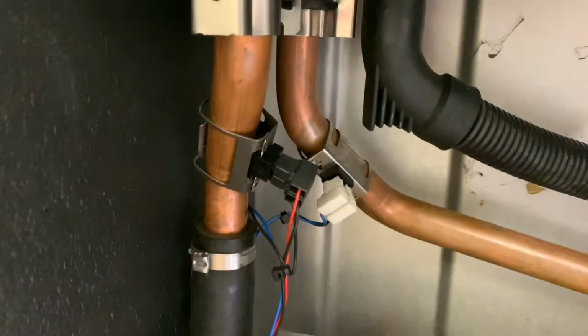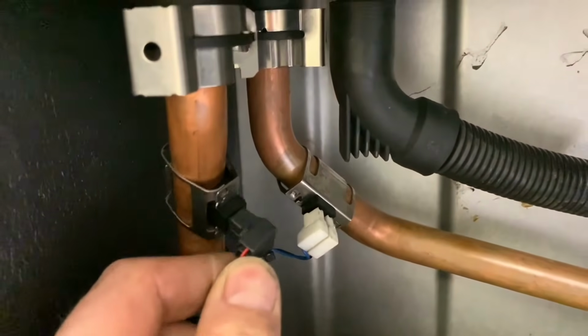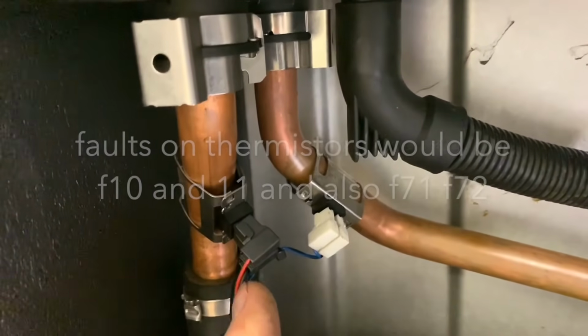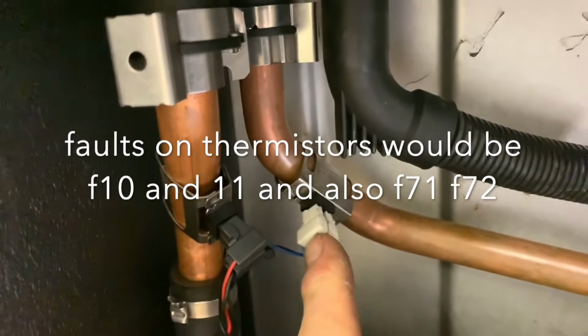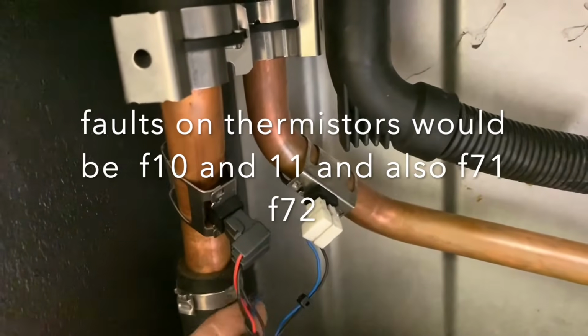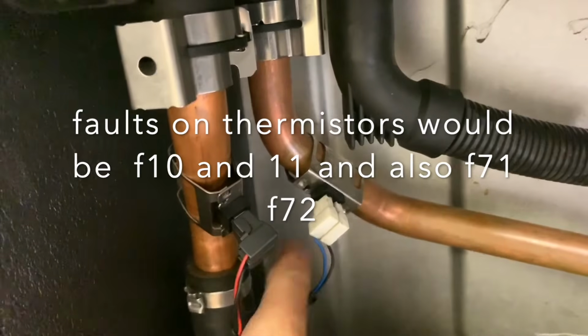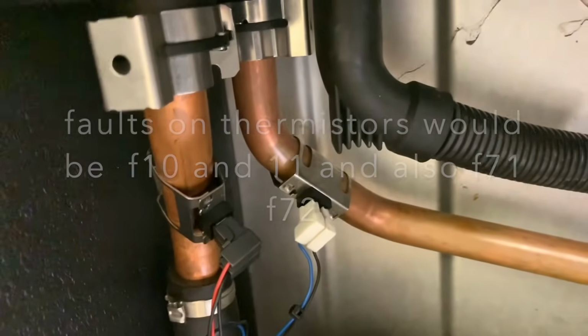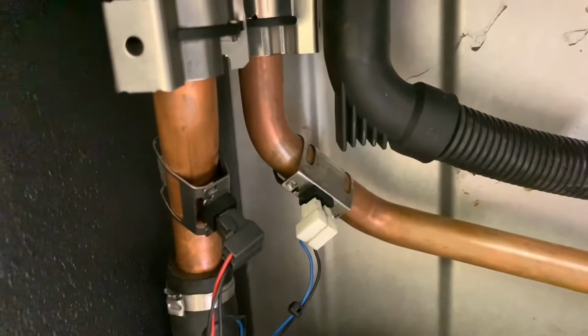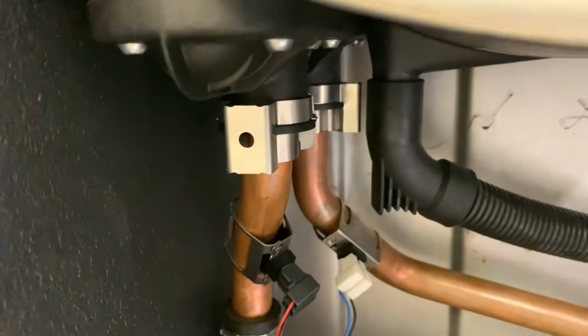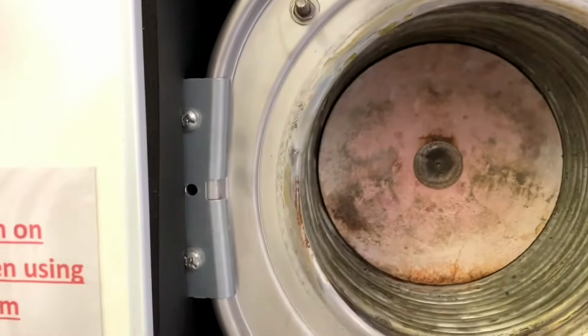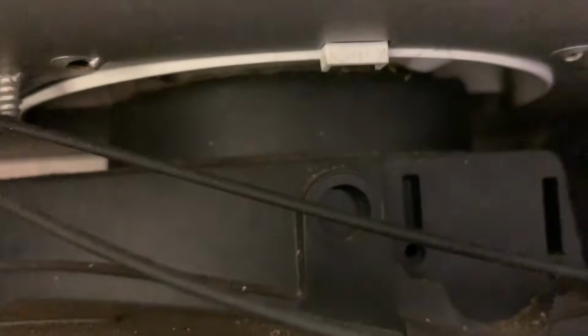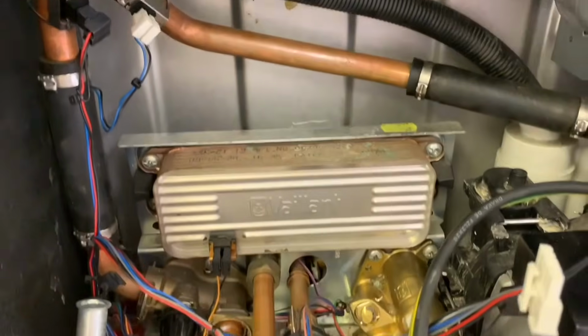What we've got here are the thermistors, okay? So this is the one on the flow pipe and then this is the return pipe. And you can see the wires are colour coded red and blue, so you get them on the flow and the return. Okay, so it's important that they stay the right way. Taking this heat exchanger out is dead easy. There's just some clips and these 4 screws on the front here, but we ain't going to be taking it out today. So you can see at the top here where the air comes in for combustion and then goes round the side and then gets drawn in through the silencer.